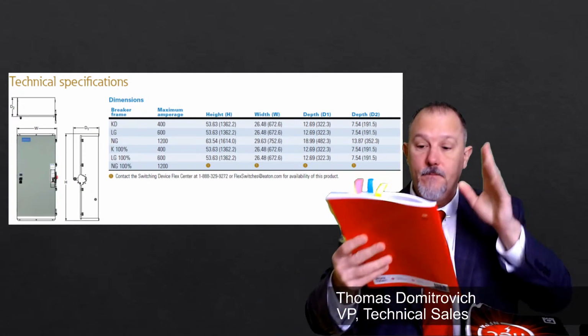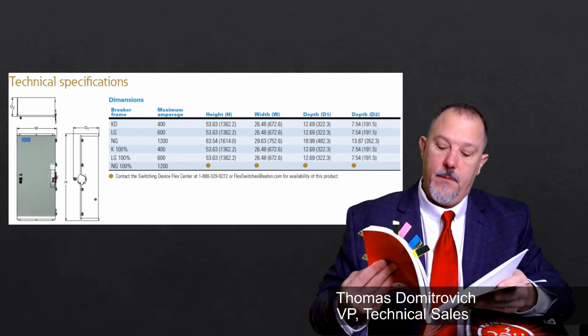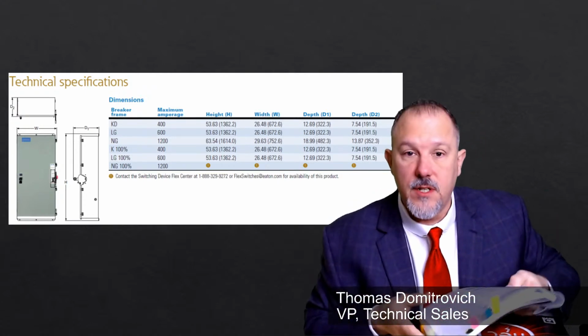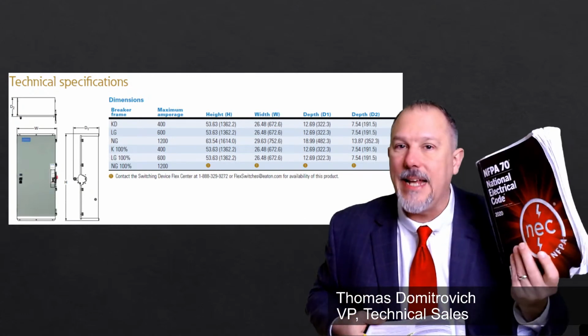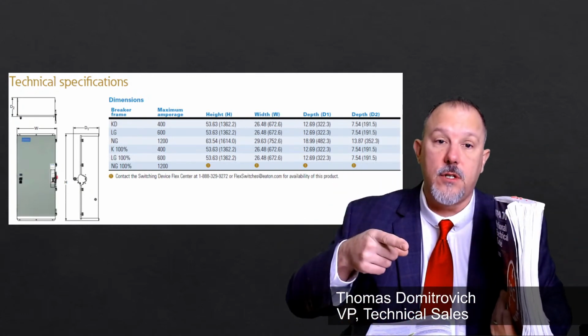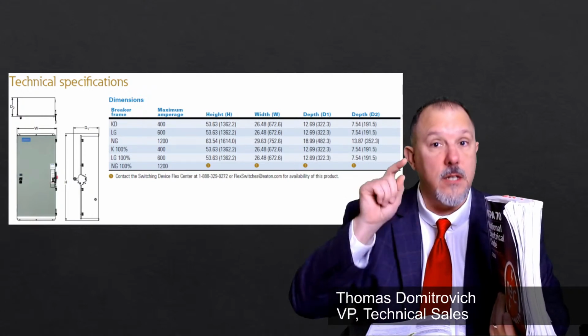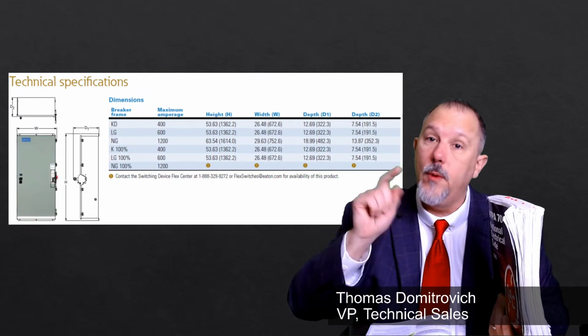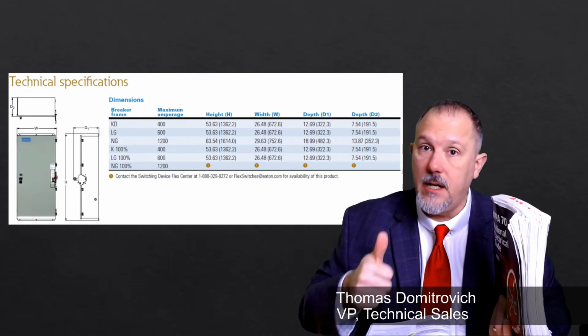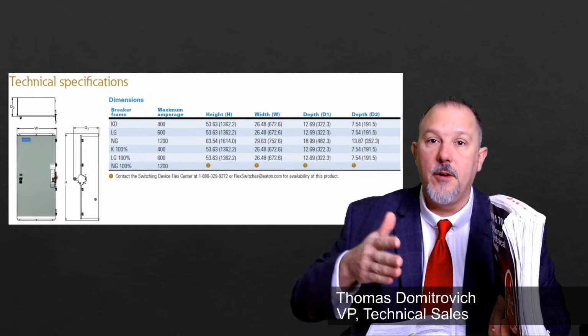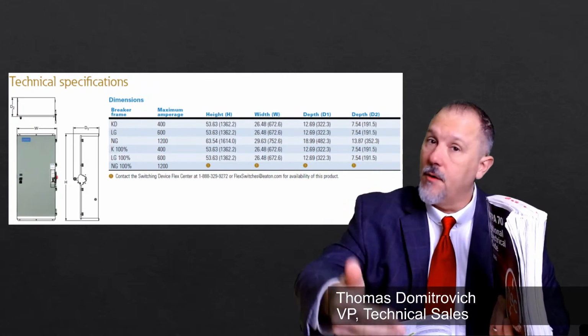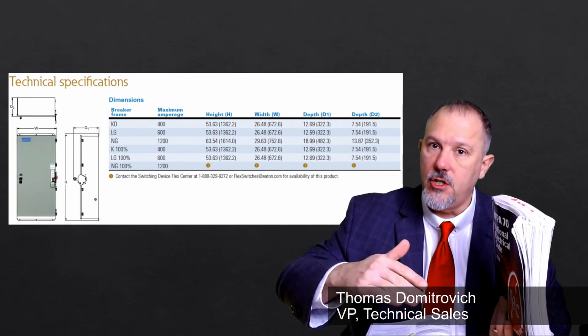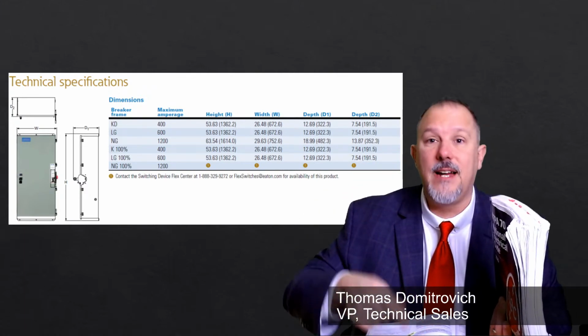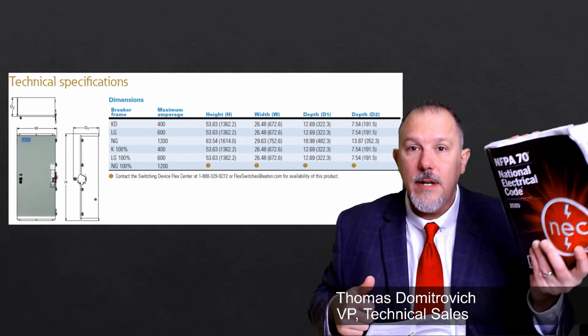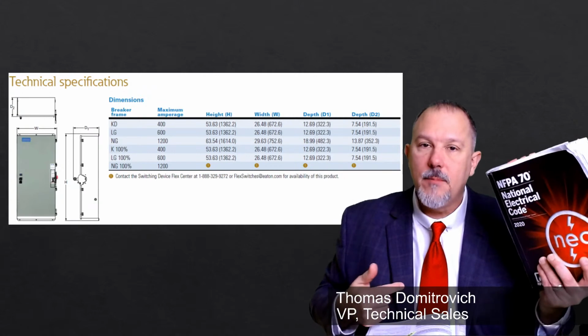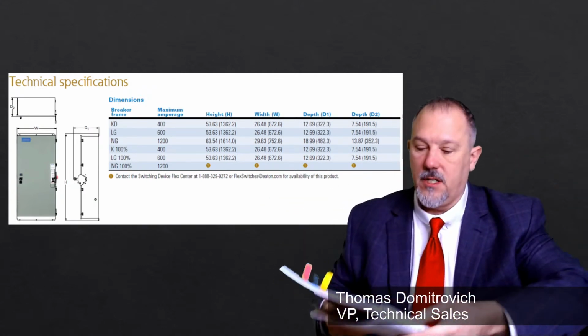Let's talk a little bit about all the cool stuff. Here are some of the references that this product, outside of 240.87, and we have 240.67 solutions for these as well. Right now, since the question came in on the enclosed circuit breaker, that's what I'm focusing on. But we have a fusible disconnect switch with an arc reduction maintenance switch on it, and it's amazing as well. It helps you get those lower arcing currents. Remember, the further down the power distribution system you are, the lower the voltages, the lower those arcing currents are, the longer the clearing times, the higher the incident energy. 240.87 and 240.67, 1200 amps and above. 2023 is moving it to 1000 amps and above.